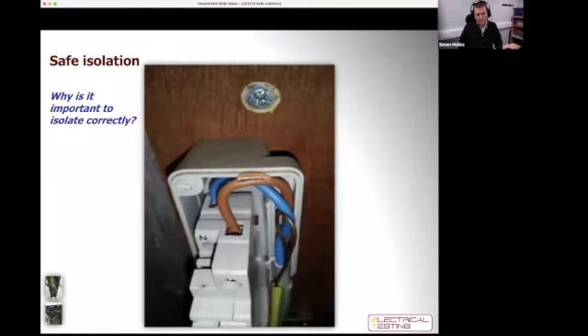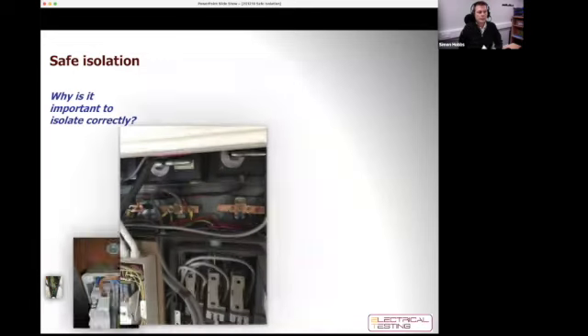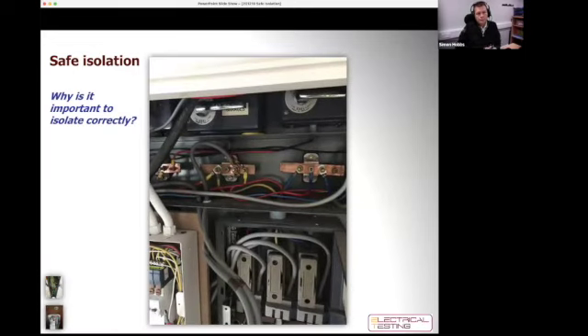Sometimes there may be mechanical damage that you don't see before you remove the cover. So if I haven't switched off and isolated this device before removing the cover, the copper conductor under that brown insulation would be live, and I may be able to put my finger on it and get an electric shock. So clearly some mechanical damage could have occurred. Another scenario is that not everyone demonstrates their competence. This is a cover of a trunking that's been removed, and behind the cover are homemade, uninsulated, bare copper terminals that are live. So if I haven't isolated the installation correctly before I've taken that trunking cover off, I'm exposing myself to unnecessary danger. So these are the moral reasons why we need to isolate, as well as the legal reasons.